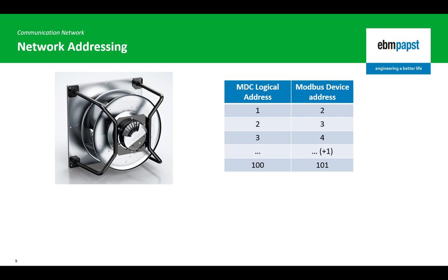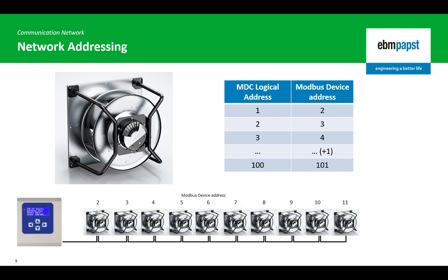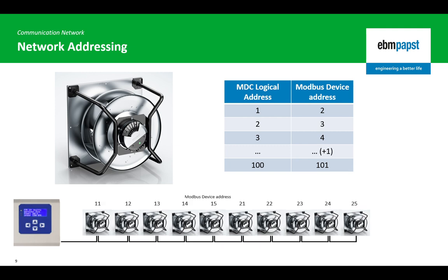The MDC does not accept gaps in the addresses of the fans. For example, a 10-fan array with device addresses between 2 and 11 is acceptable. A 10-fan array with device addresses 11 to 15 and 21 to 25 is not acceptable.